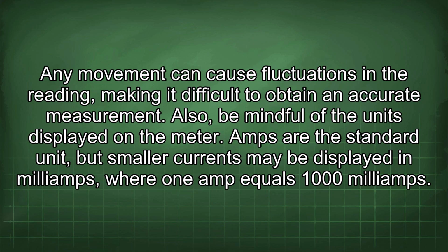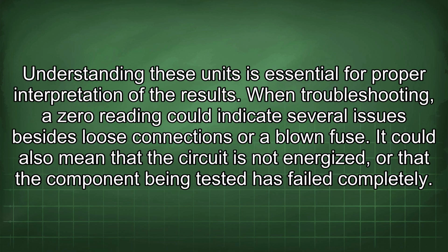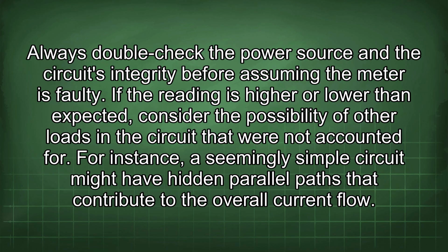Also, be mindful of the units displayed on the meter. Amps are the standard unit, but smaller currents may be displayed in milliamps, where 1 amp equals 1000 milliamps. Understanding these units is essential for proper interpretation of the results. When troubleshooting, a 0 reading could indicate several issues besides loose connections or a blown fuse. It could also mean that the circuit is not energized, or that the component being tested has failed completely. Always double-check the power source and the circuit's integrity before assuming the meter is faulty.